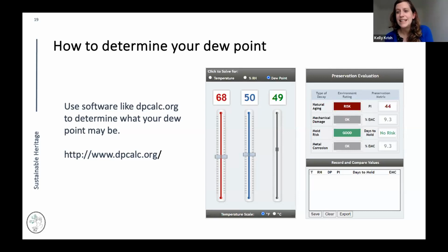Others might decide that they don't mind staying further out, but they want to eat at really nice restaurants. That's where you come to this balance between temperature and RH: when you have that fixed dew point, you can raise the temperature and it's going to drop the RH, but not every combination is going to be possible at every dew point. Hopefully that's a helpful metaphor, but that's how the three are related. Are there any questions?